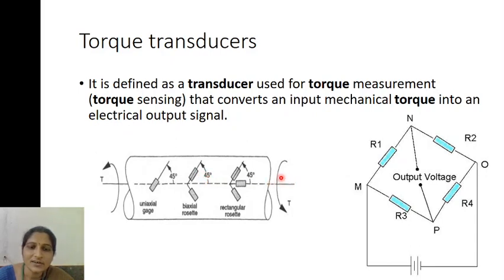Whenever a torque is applied on the shaft, in this direction it is applied in the clockwise direction, and at the other end it is applied in the anti-clockwise direction. There is a twisting force acting on the shaft. Because of that twisting force, the strain gauge's resistance changes. When the resistance changes, that means there is a torque applied. These strain gauges are connected to a Wheatstone bridge, so that there is a deflection in the galvanometer, and the deflection of the galvanometer will indicate how much torque there is, in terms of voltage. In this way, you can measure the torque.